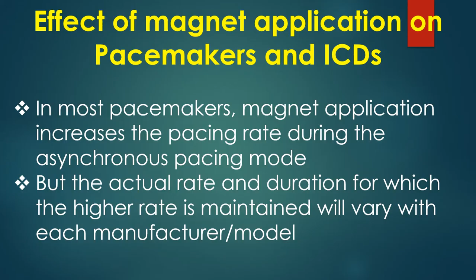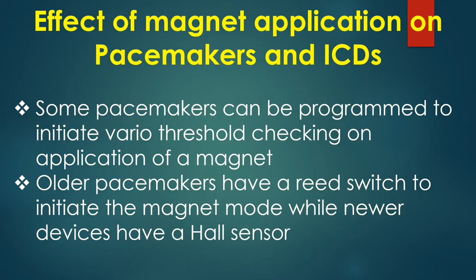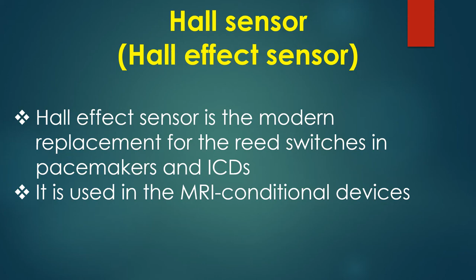Some pacemakers can be programmed to initiate vario-threshold checking on application of a magnet. Older pacemakers have a reed switch to initiate the magnet mode, while newer devices have a Hall sensor. Hall effect sensor is the modern replacement for the reed switches in pacemakers and ICDs. It is used in MRI conditional devices.